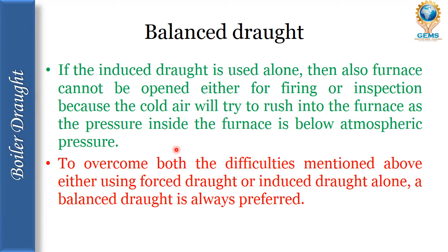In an induced draft system, the pressure inside the boiler system is maintained lower than the atmospheric pressure, so that in any case for firing or inspection, if you open the boiler system, the outside high pressure atmospheric cold air rushes into the furnace and destroys the pressure balance. So induced draft alone cannot be used.